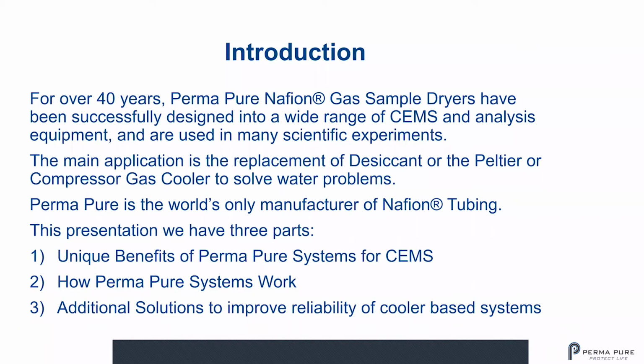As an introduction, for over 40 years, Permapure's Nafion gas sample dryers have been successfully designed into a wide range of CEMS and analysis equipment and are used in many scientific experiments. Particularly with CEMS, we have over 30 years of experience building our dryers and developing sampling systems for CEMS systems. So we have a long history in this field. And the main application is the replacement of the desiccant or the Peltier or compressor gas cooler to solve water problems. Specifically for CEMS, we're replacing the cooler. Permapure is the world's only manufacturer of Nafion tubing.